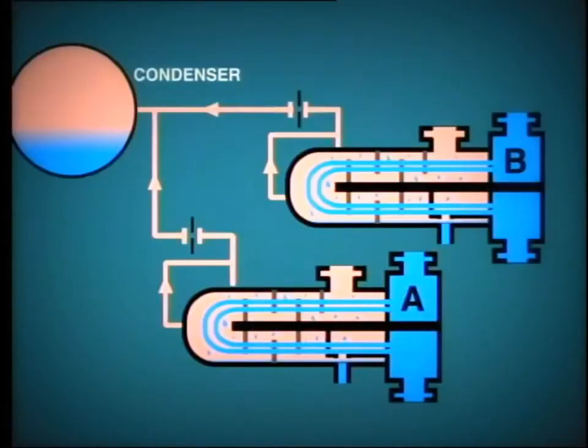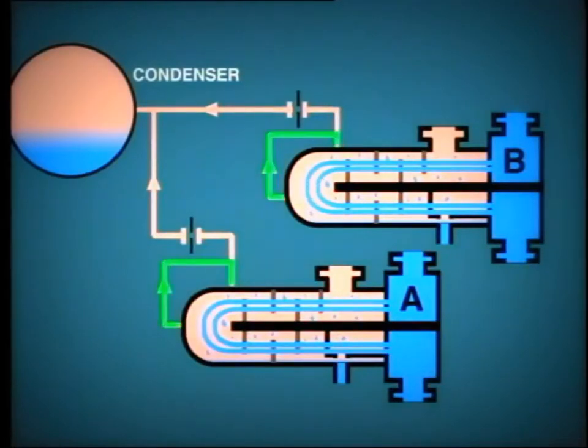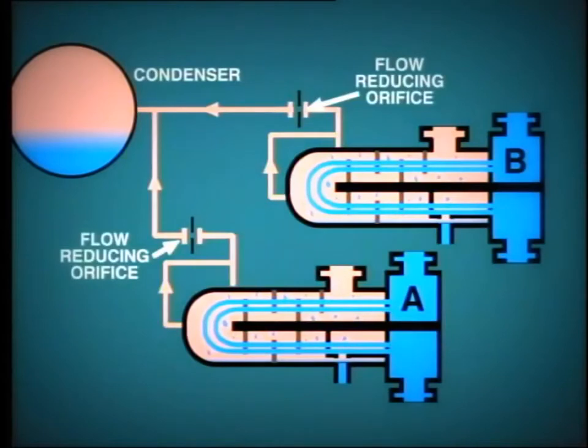In most plants, the venting arrangements are as shown here. You can see that the upper and lower vents from the heater join together and pass through this orifice direct to the condenser, which is of course operating at much lower pressure. The objective of the orifice is to reduce the flow, otherwise excessive steam may pass through the vent in addition to air and carbon dioxide.